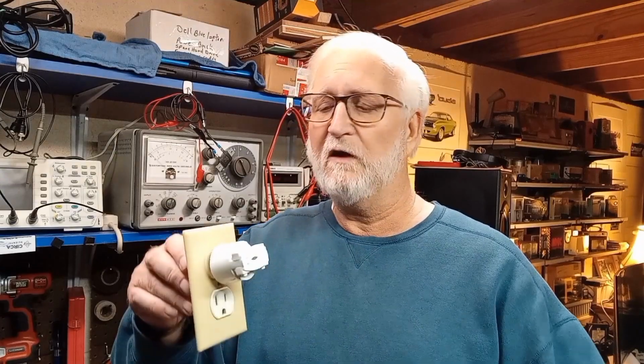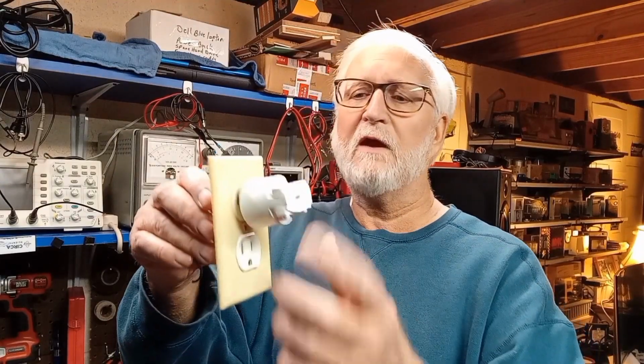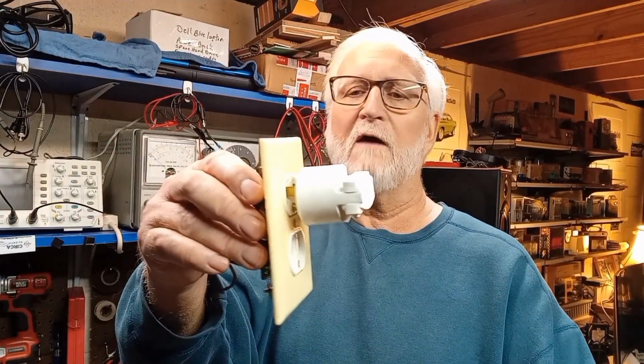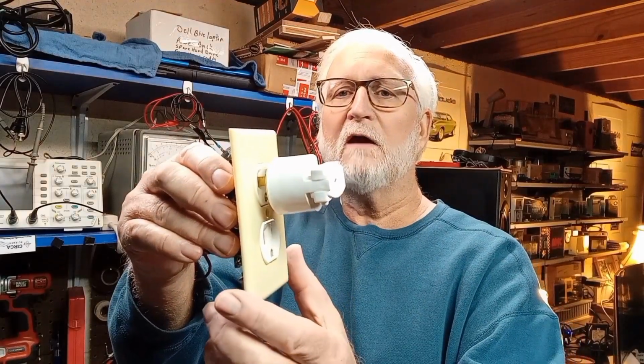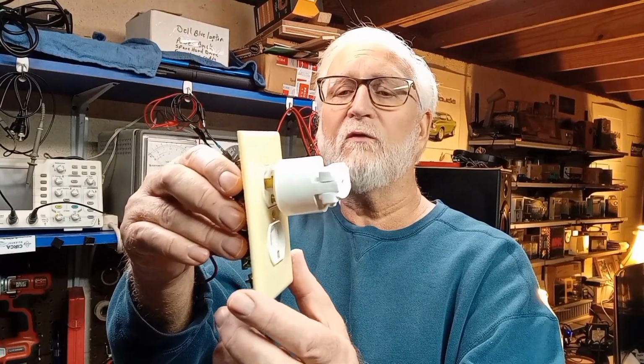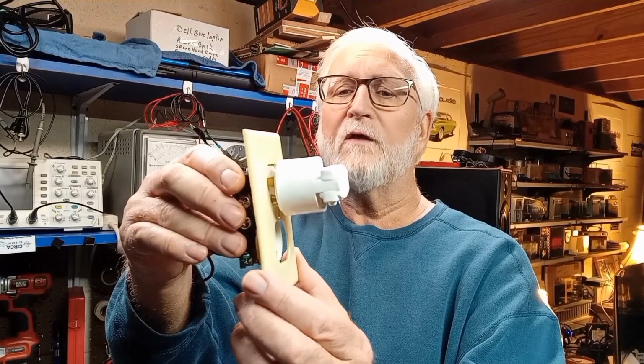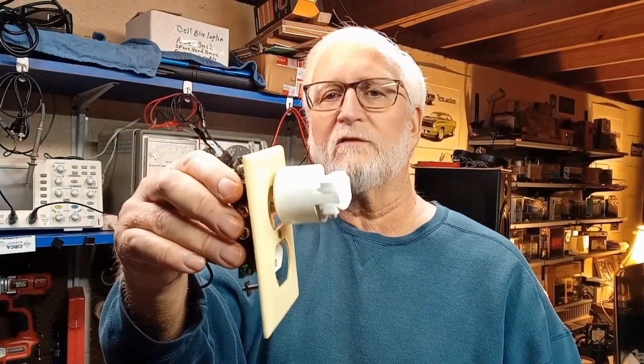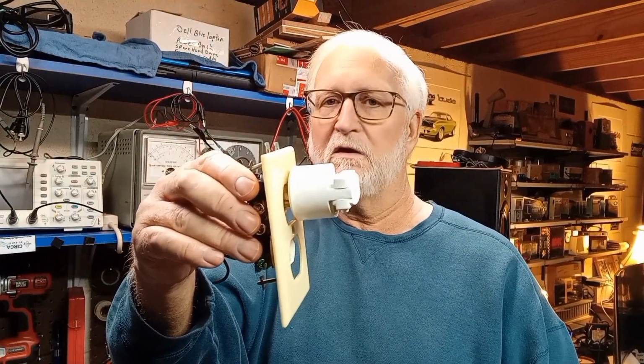I've had to change a number of these because what happens is, if staff is plugging something in and out with the ground prong down, guess what? They don't notice that screw fell out, and that thing will fall right down across the hot and the neutral, and bam, you've had some sparks.